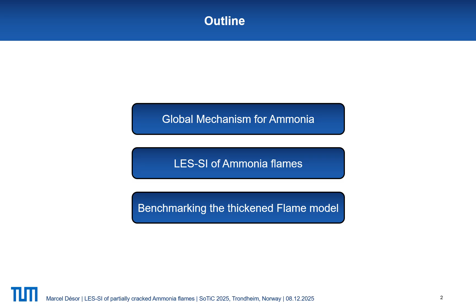Okay, why do we care about ammonia in the context of thermoacoustics? Well, if we want to burn ammonia in a gas turbine combustor, for example, if we want to mitigate peak loads in the morning or in the evening, we could burn it directly. However, ammonia burns really poorly and is hence prone to blow off, or in general limits the operability range of the gas turbine, and additionally it has very undesirable flame characteristics, yielding very long flames that are prone to, for example, flame wall interactions.